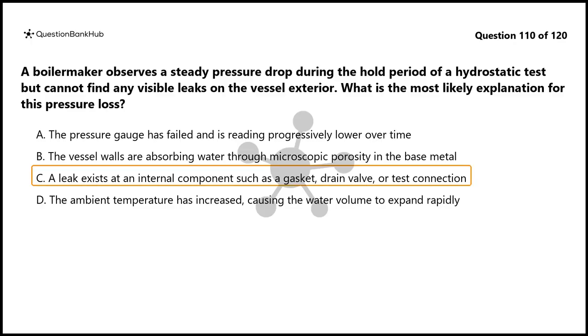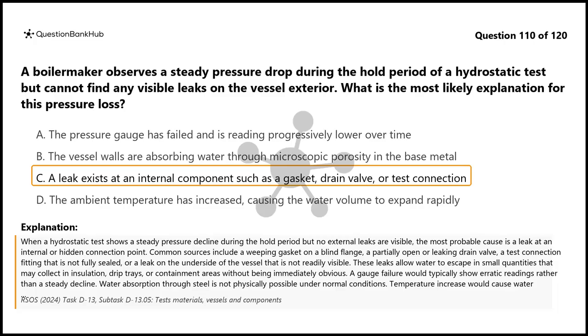The correct answer is C. When a hydrostatic test shows a steady pressure decline during the hold period but no external leaks are visible, the most probable cause is a leak at an internal or hidden connection point. Common sources include a weeping gasket on a blind flange, a partially open or leaking drain valve, a test connection fitting that is not fully sealed, or a leak on the underside of the vessel that is not readily visible.